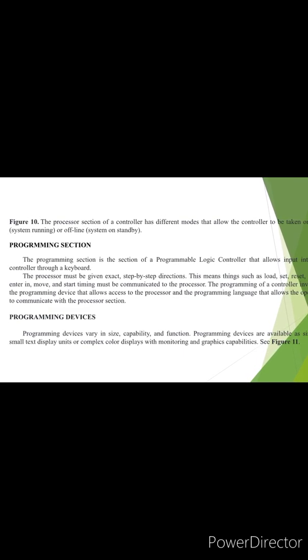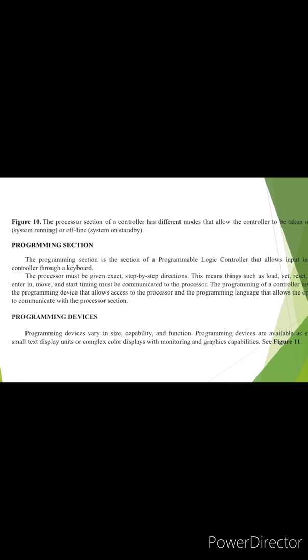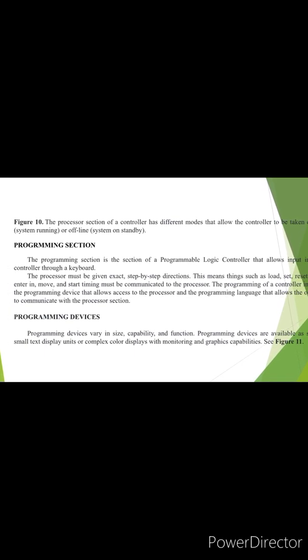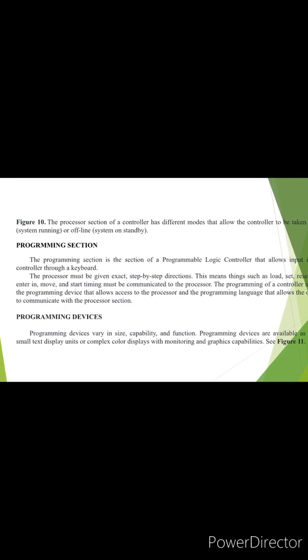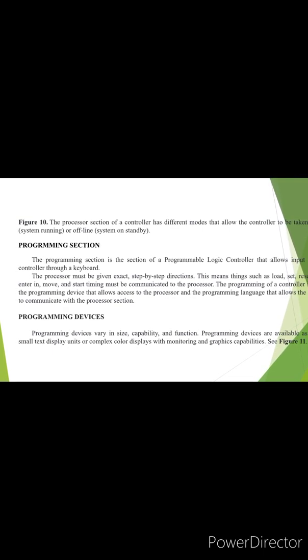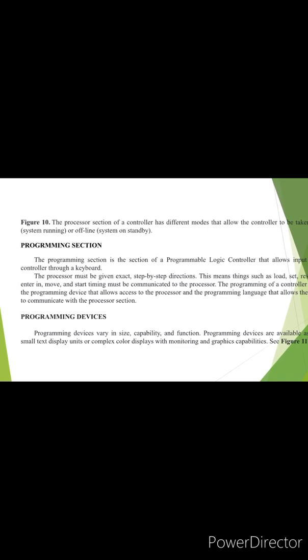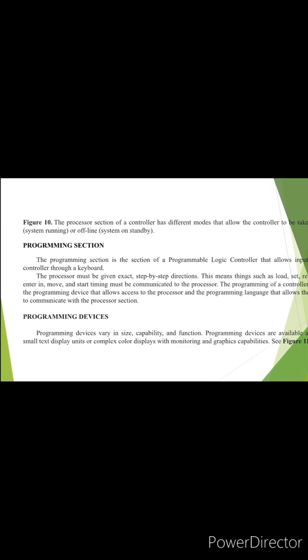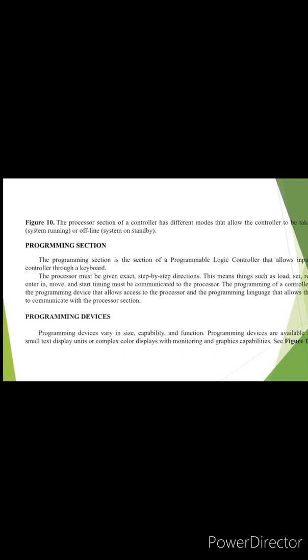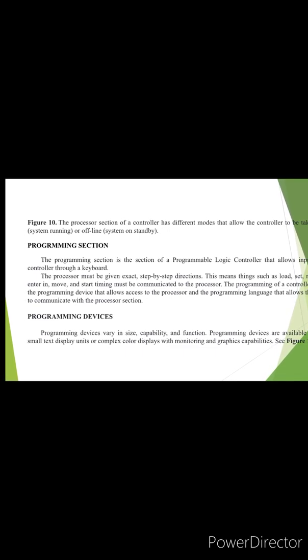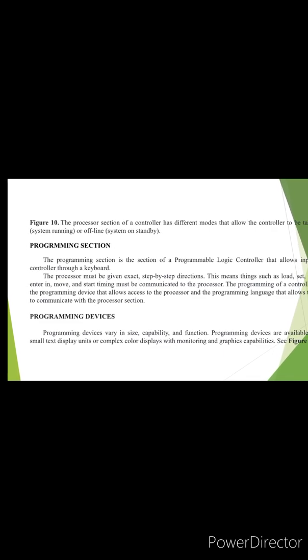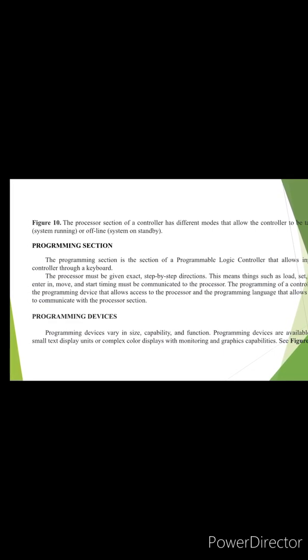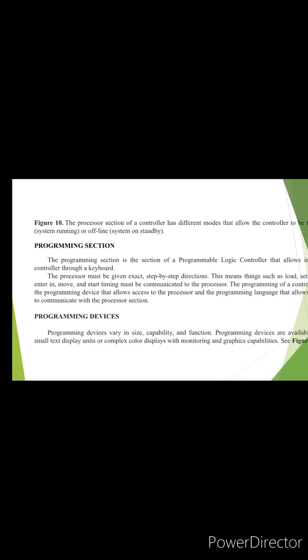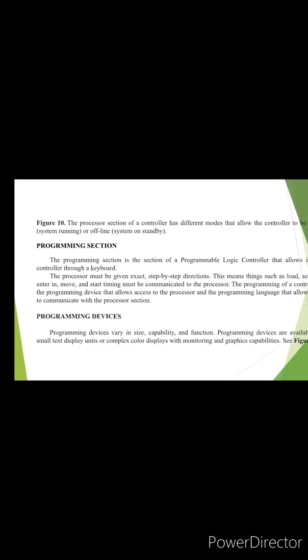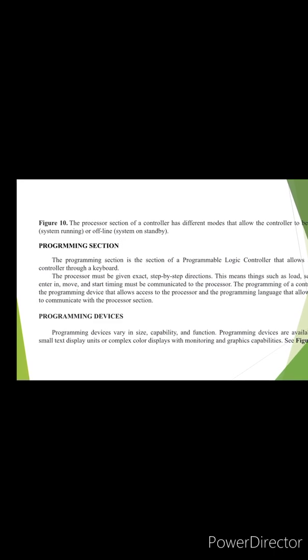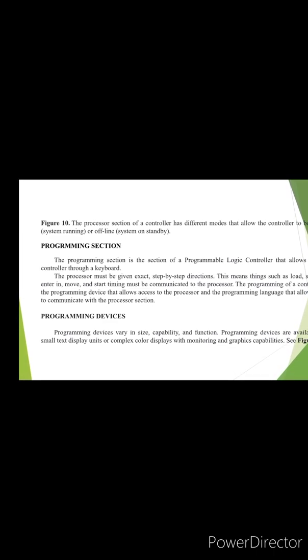Programming section. The programming section is the section of a programmable logic controller that allows input into the controller through a keyboard. The processor must be given exact step-by-step direction. This means things such as load, set, reset, clear, enter, move, and start timing must be communicated to the processor. The programming of a controller involves the programming device that allows access to the processor and the programming language that allows the operator to communicate with the processor section.